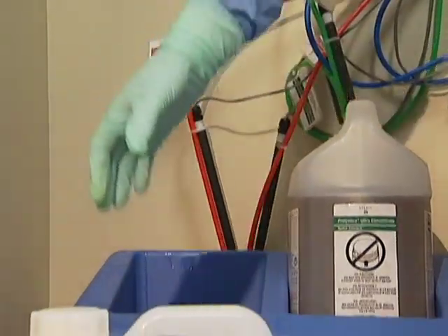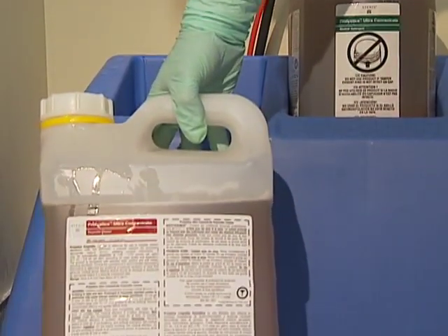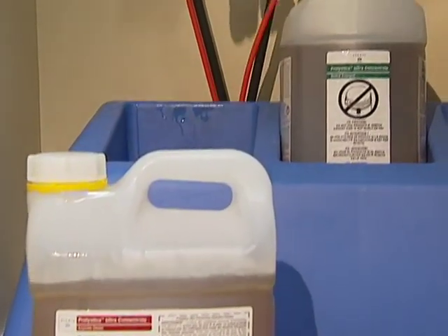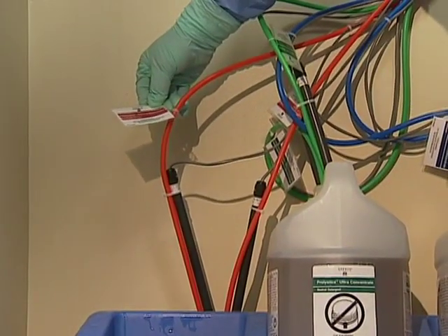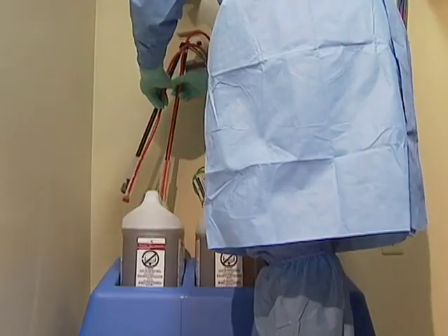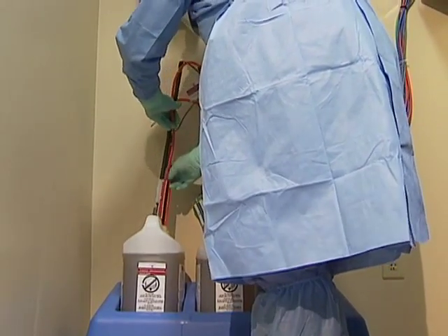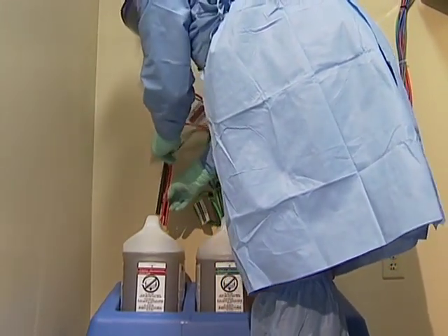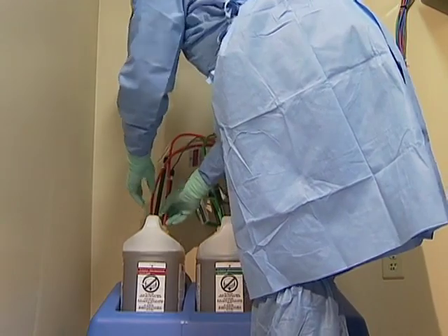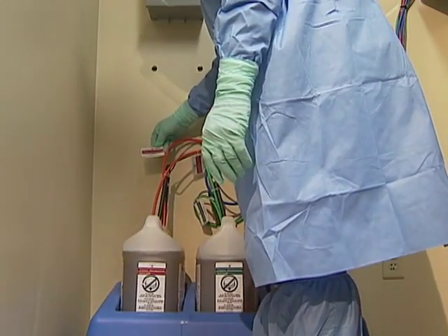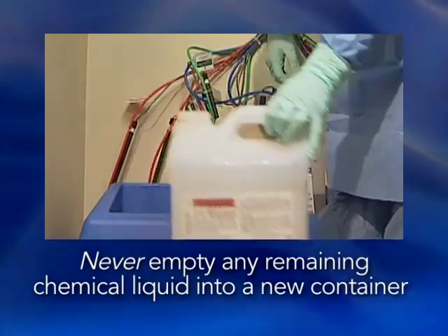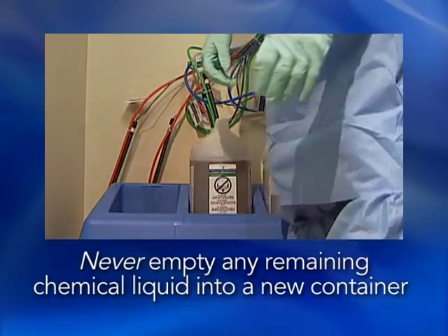Note that the tubes are color-coded to correspond with their appropriate Prolystica Ultra Concentrate containers. Check to make sure you're selecting the correct chemical. Once you have verified the correct chemical container, insert pickup tube and sensor into the new container. Finally, replace the old container with the new one. For safety reasons, never empty any remaining chemical liquid into the new container.